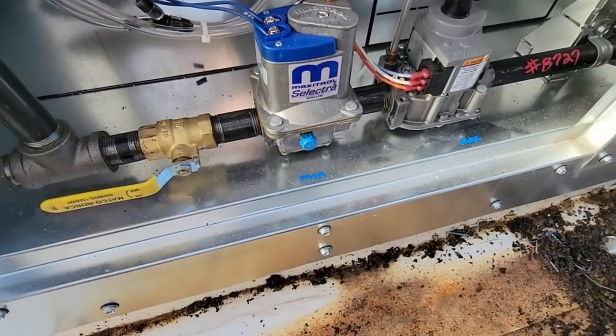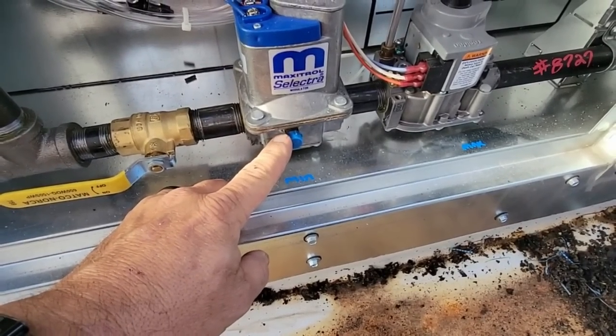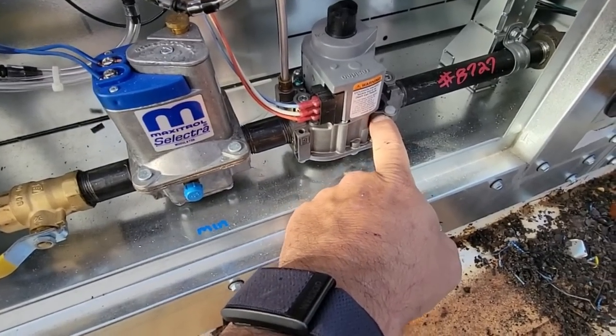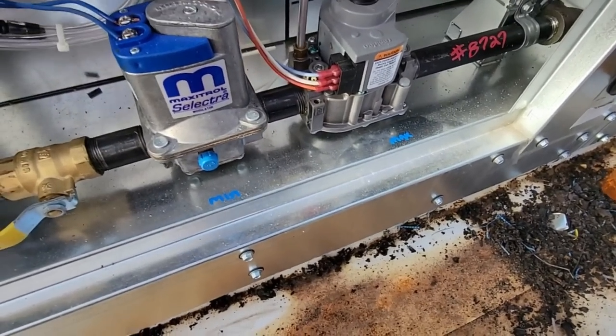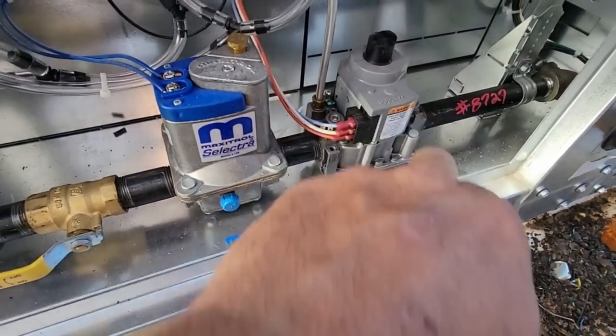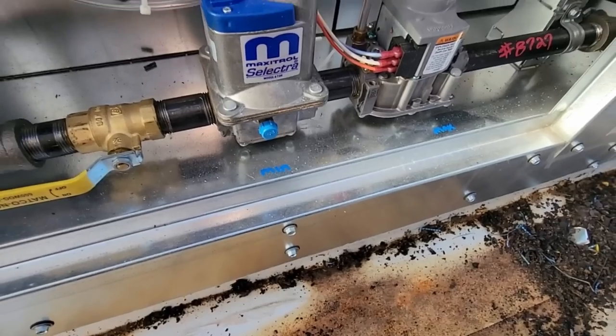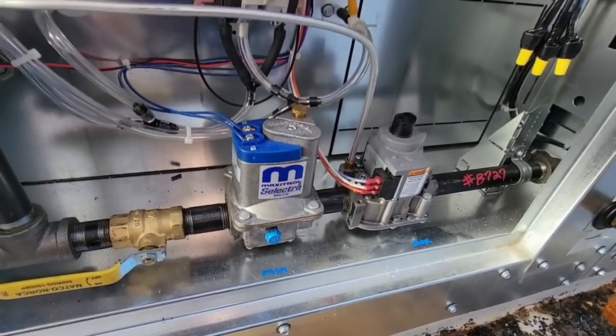When we get ready to fire it off, here's where our minimum firing rate is gonna be adjusted, and right on the traditional gas valve is where our maximum is gonna be adjusted. Like I said, this is nothing but an open-close switch here. Let's check our voltage and see what our transformers are tapping in at.